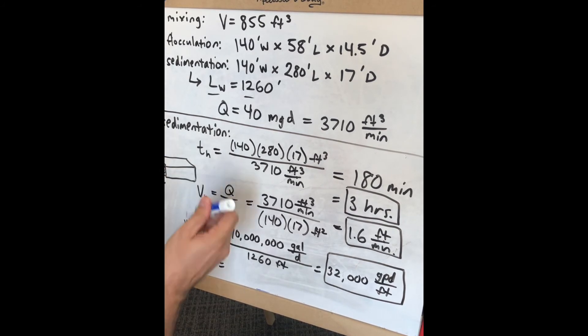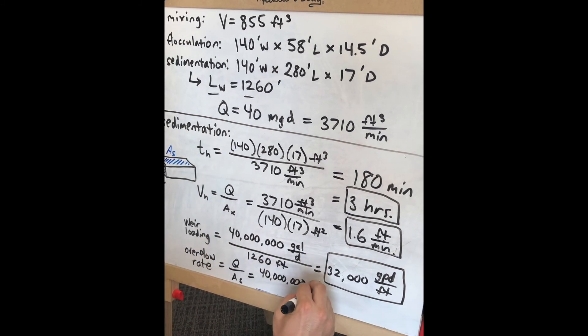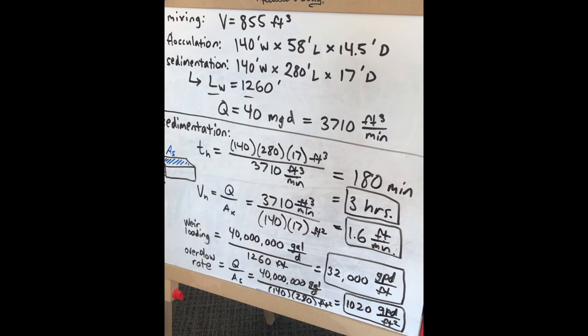The overflow rate equals the flow rate divided by the surface area, giving 1020 gallons per day per square foot.